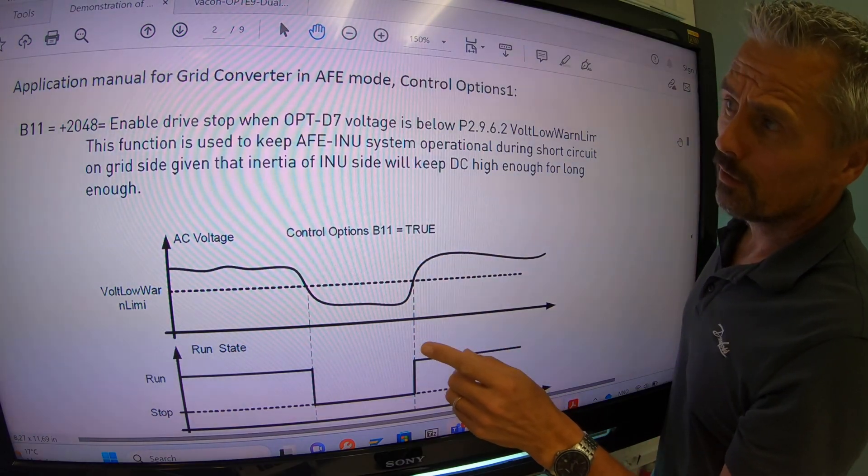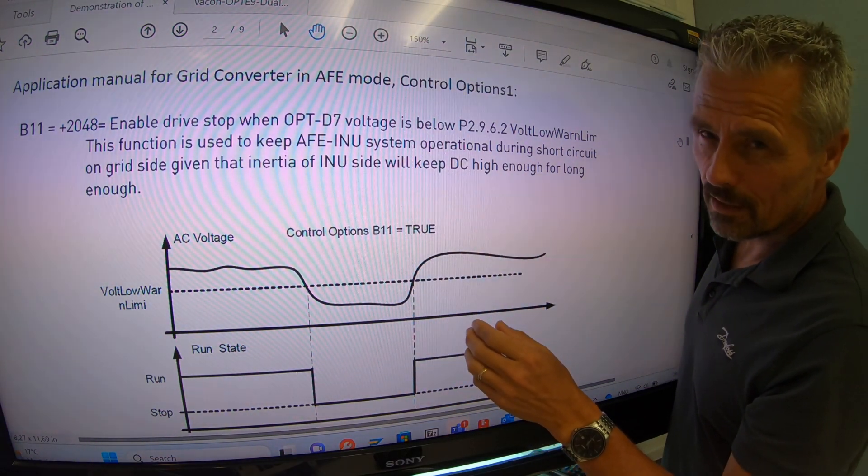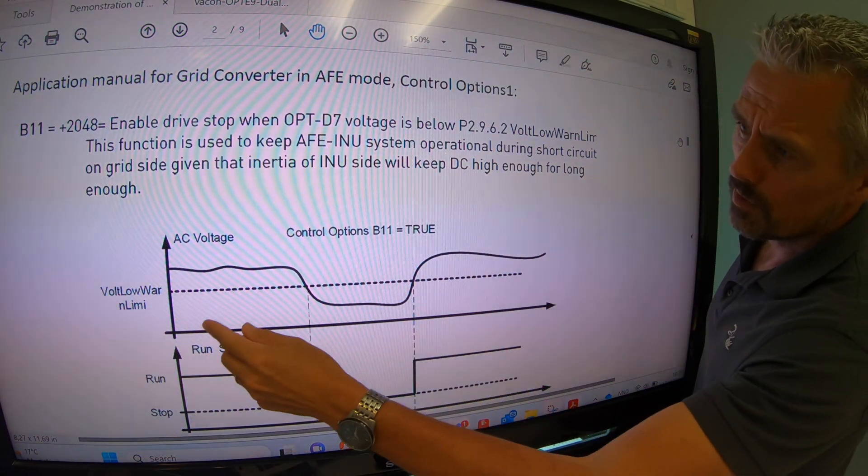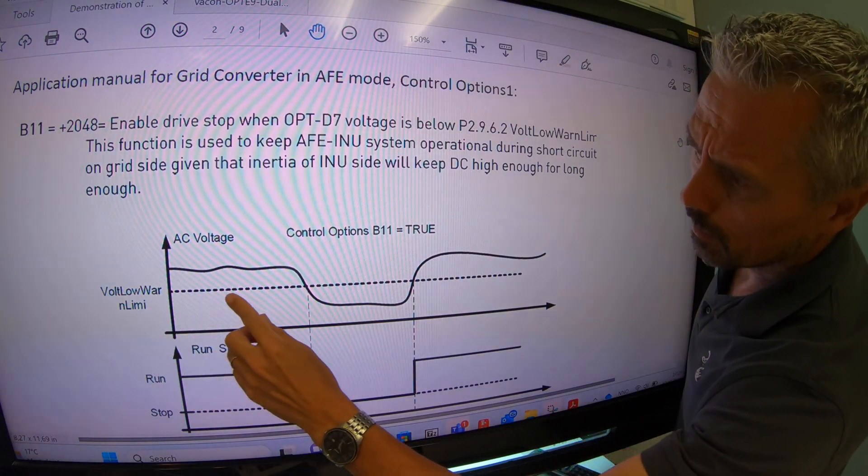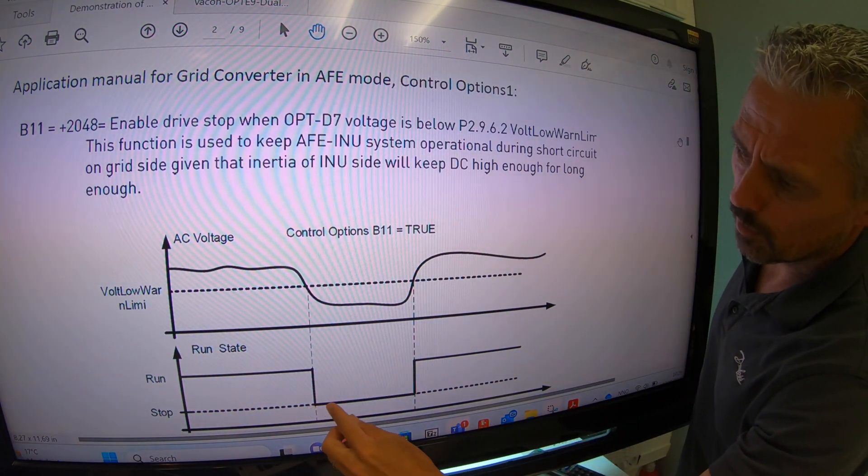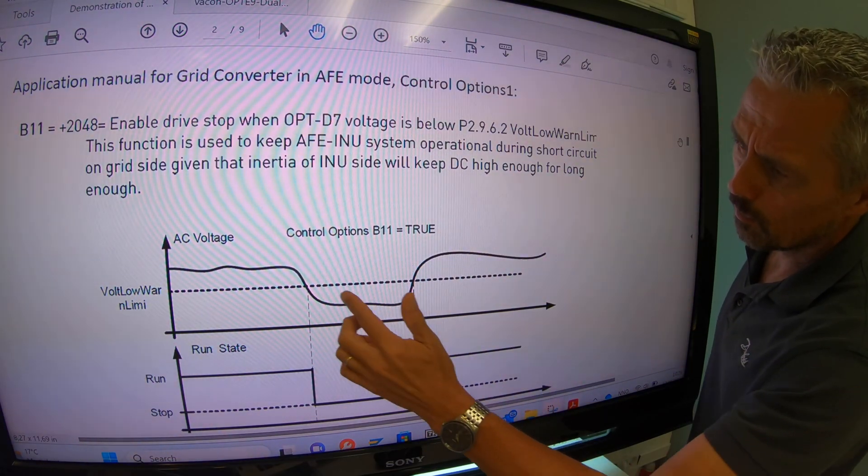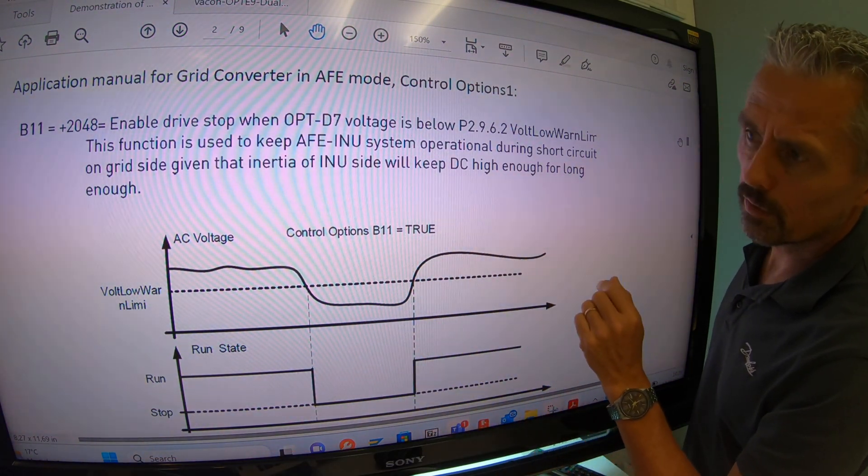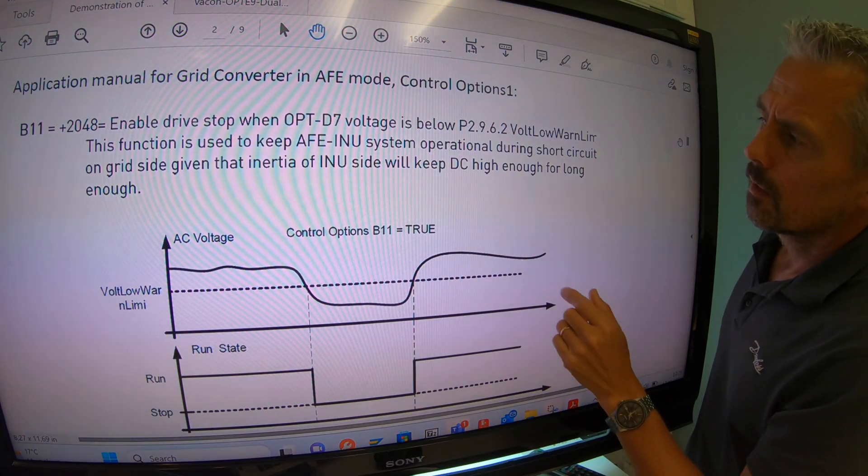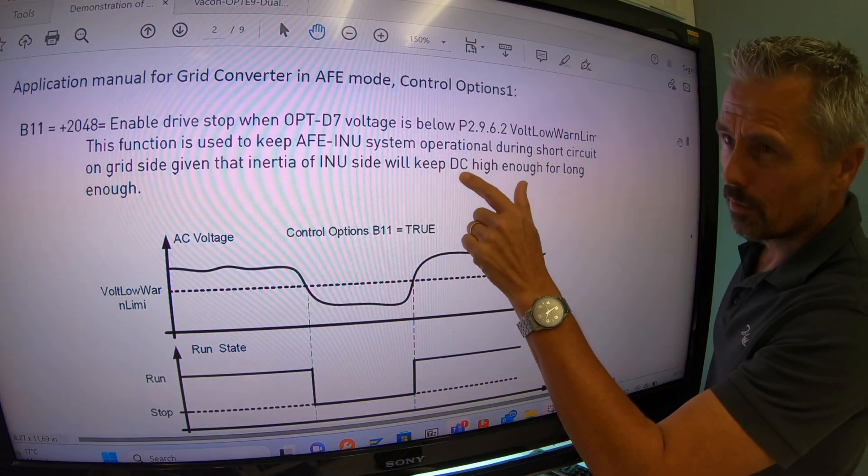In the application manual for the grid converter, the bit 11 functionality is explained. Here we see how the voltage low warning triggers the disabling of the running of the drive and keeps it running again when the voltage goes above the warning level. Note that the DC link cannot go to zero.